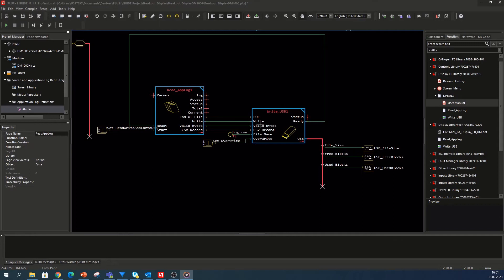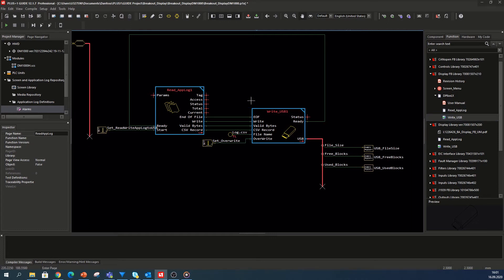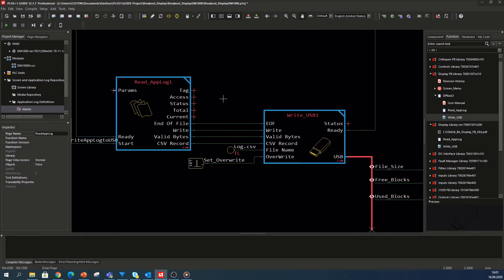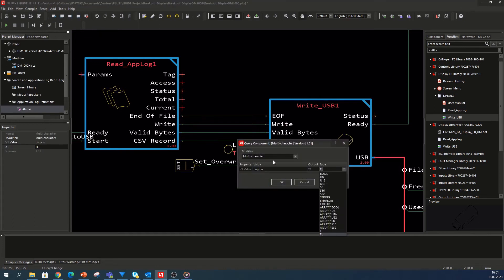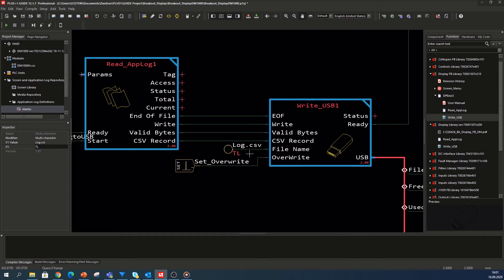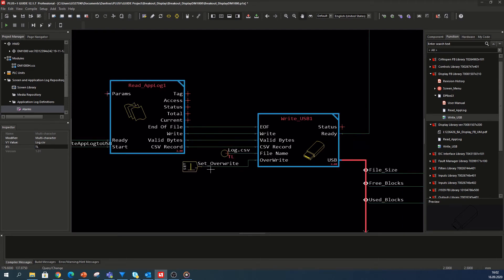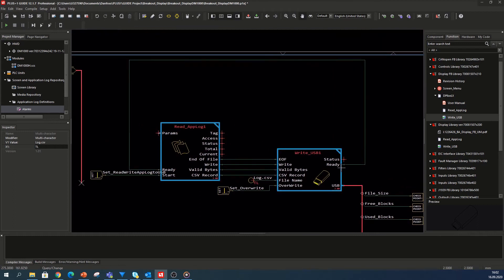Since there is a detailed description available of each block's inputs and outputs, I will show the practical part only. Starting by dragging each block — read app log and write USB — from the library and dropping it into my GUIDE code drawing area. I connect all the mandatory inputs of the write USB block with the respective outputs of the read app log block. Here we can see that both blocks are perfectly synchronized. For the input file name, a constant can be connected with a type TL, called text label. As mentioned in the user manual, the file name must conform to the 8.3 file name format, which means the file name cannot have more than eight characters, followed by a dot and then a three-character extension.